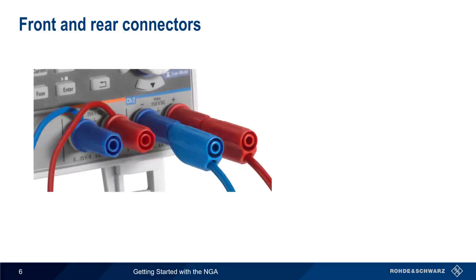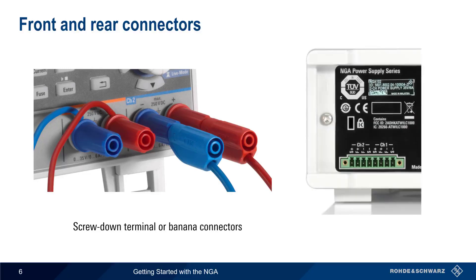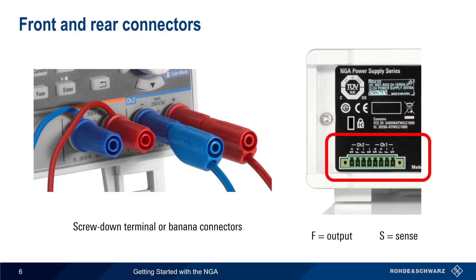On the front of the NGA, connections can be made using either screw-down type insulated terminals or pluggable banana-style connectors. Connections can also be made on the rear of the instrument at the provided terminal block, with the F terminals being for output connections and the S terminals for so-called sense connections, something we'll cover later in this presentation.